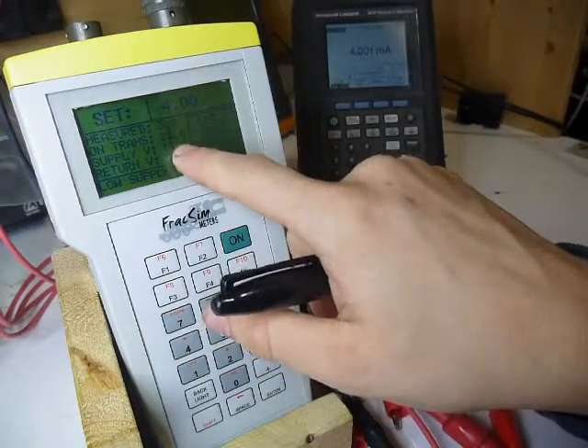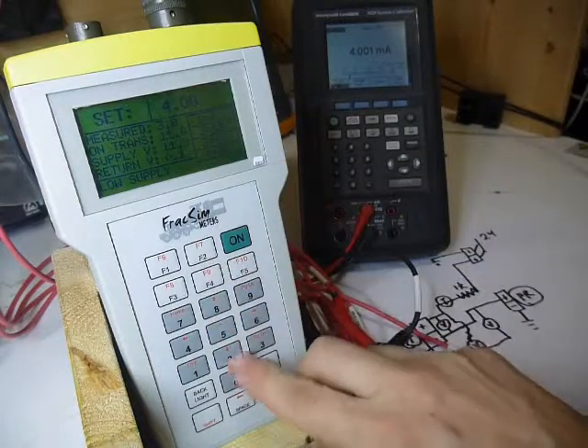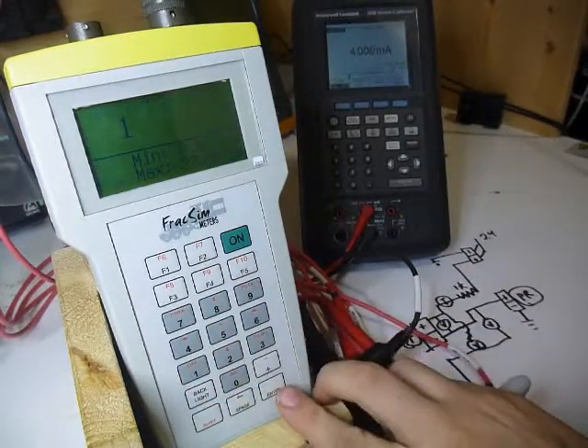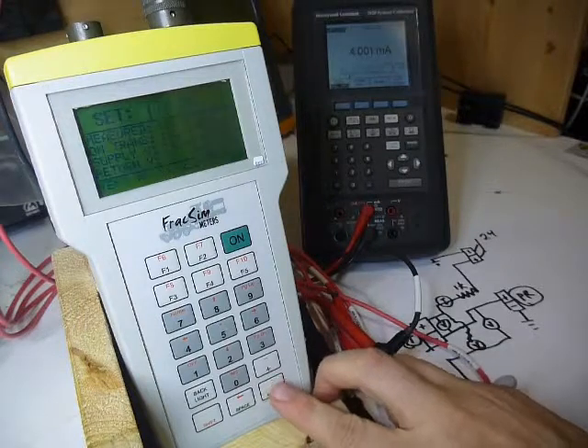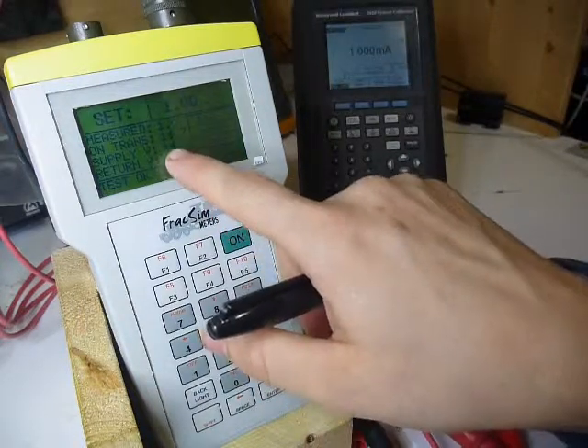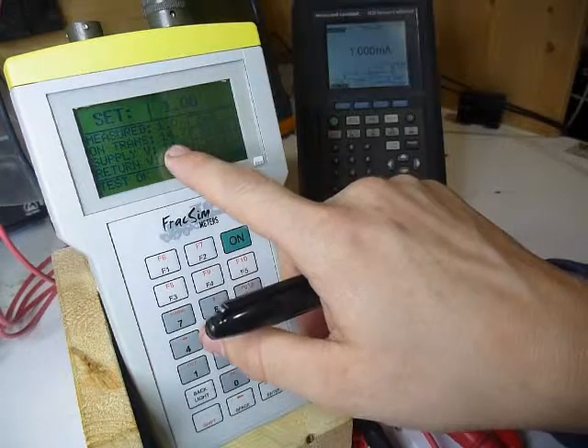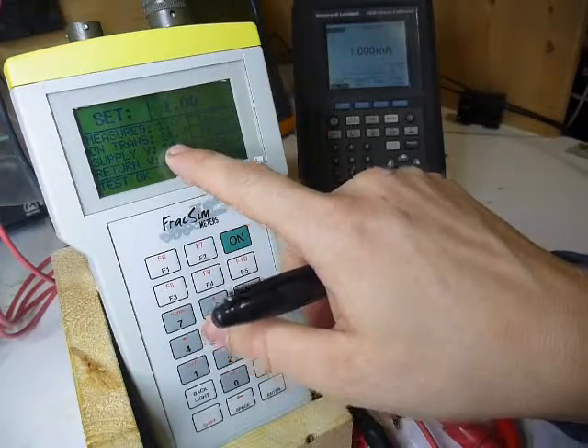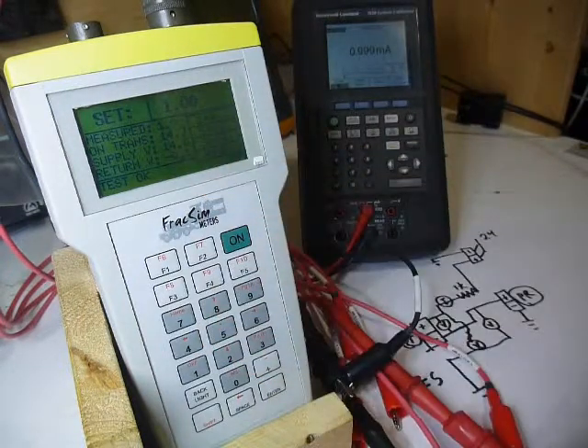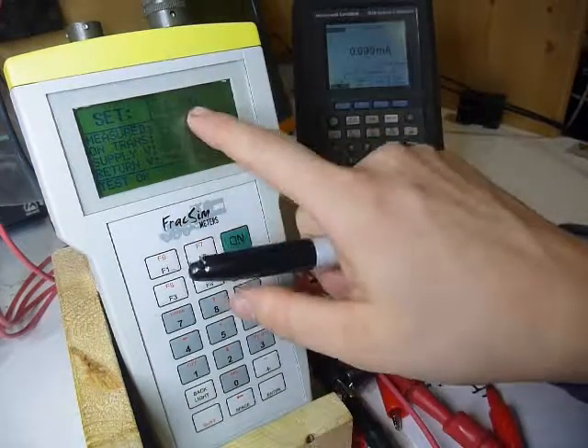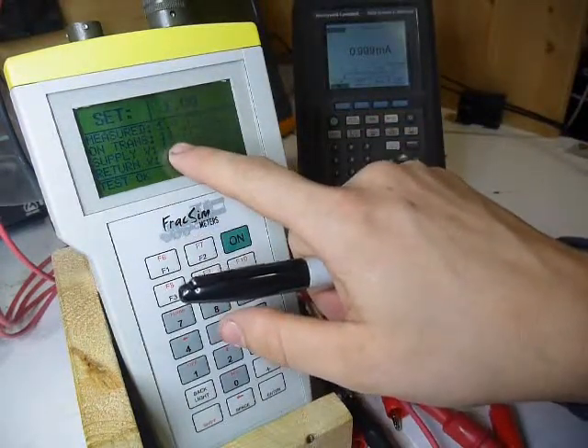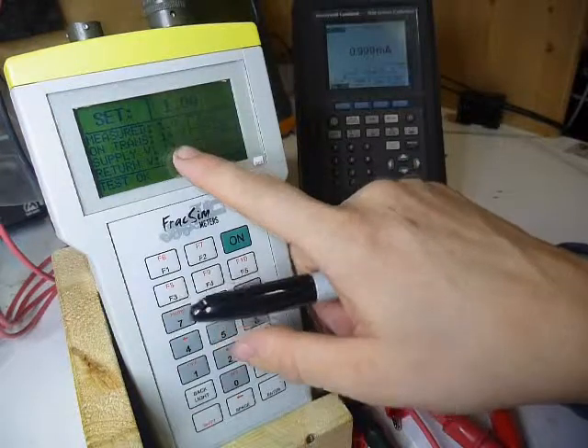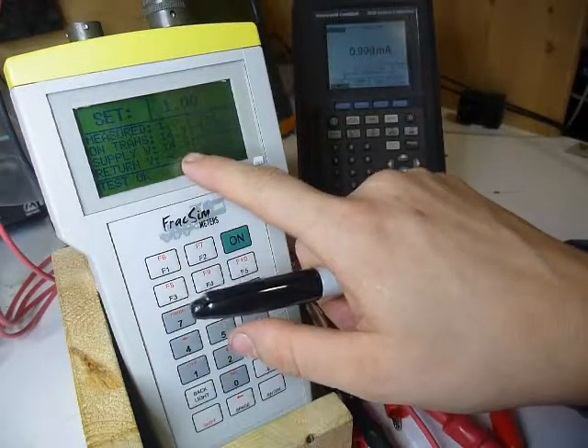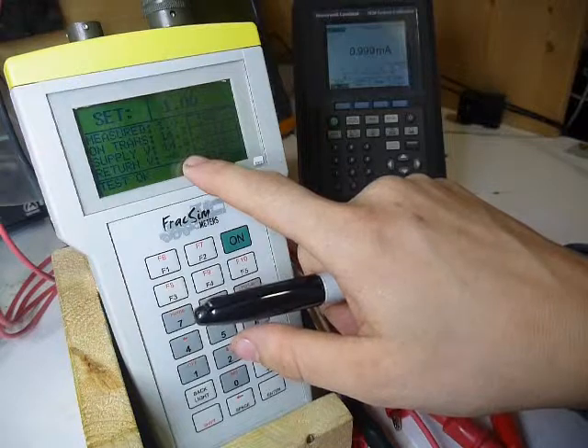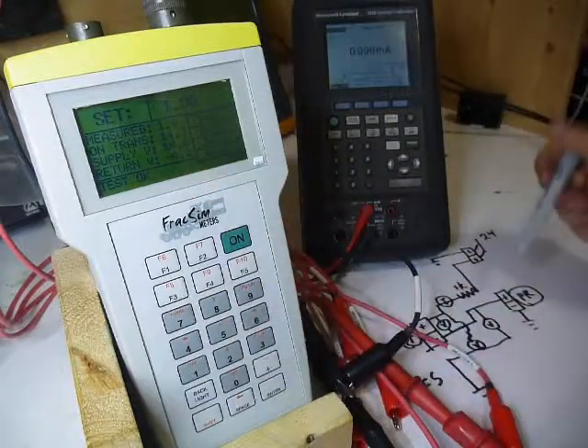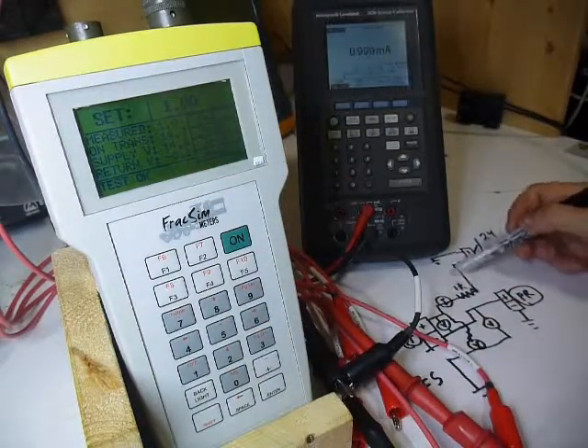And you can see, if I were to put in a different value like 1 milliamp, look at that, the voltage went up more than 2.5 volts just by changing the current down to 1 milliamp. So you can tell that by adding a little bit of current, you're having a huge voltage drop, so there's definitely an issue. And with no return voltage drop, you can tell the resistance is going to be right in the supply side.